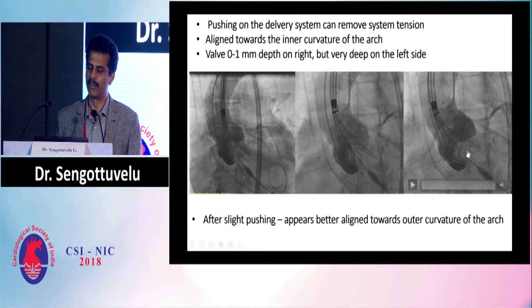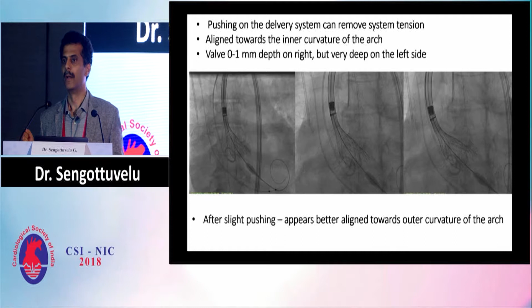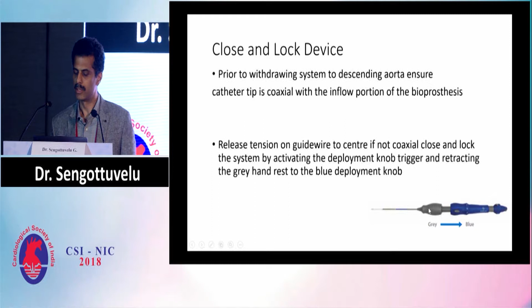Prior to withdrawing, once we complete the release, the valve is released completely, making sure that all the paddles are completely released slowly, and the last third should be a very slow release. Once the paddles are relieved and the valve is in position, we have to close and remove the system. Prior to withdrawing the system to the descending aorta, we have to make sure the catheter tip is coaxial with the inflow position. Otherwise, we can cause the valve to pop out. So we have to pull the wire a little bit, making sure it becomes coaxial, and then you can take out the nose cone, and then the gray knob is brought towards the blue knob by retracting it. And once that is done, the system can be withdrawn.